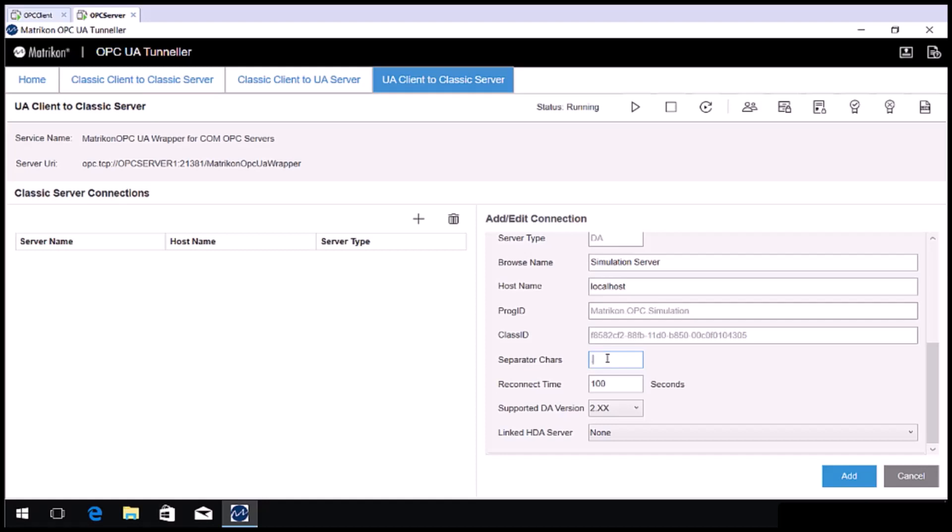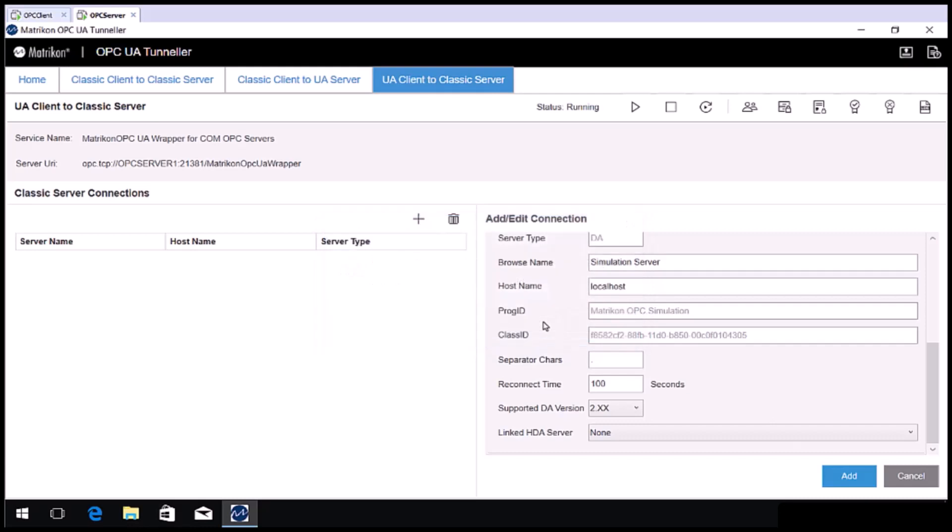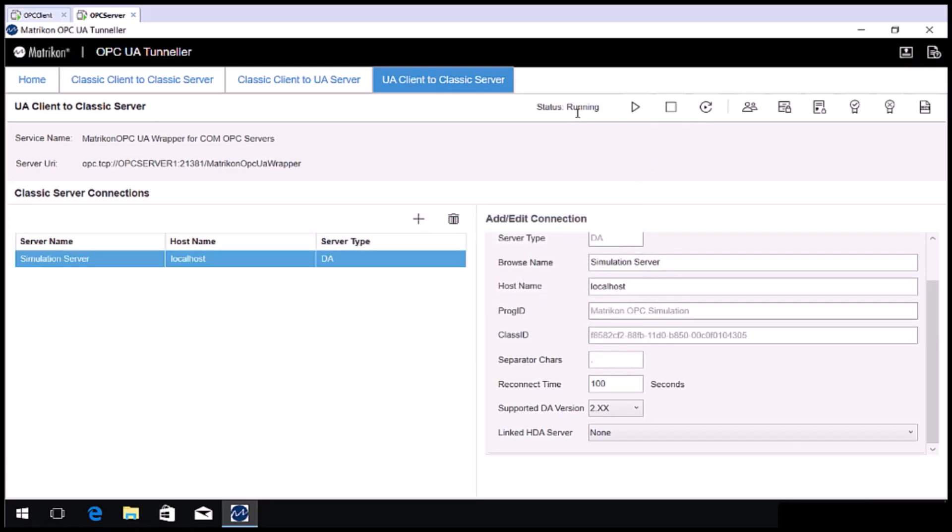If your OPC DA server supports OPC DA3, we suggest changing the supported DA version to 3.0 as this will significantly speed up browsing. Click add. If the service is already running, you will be prompted that a restart will take place. If not, start the service by clicking the play button and confirm the status is running.